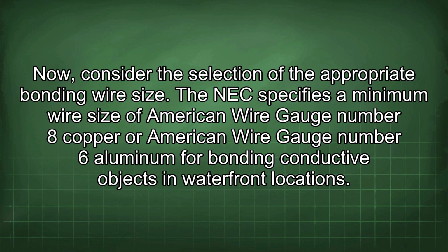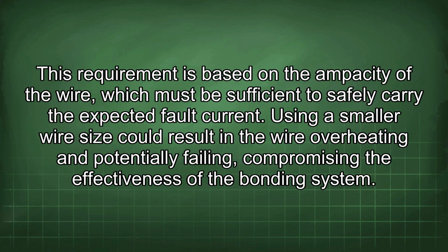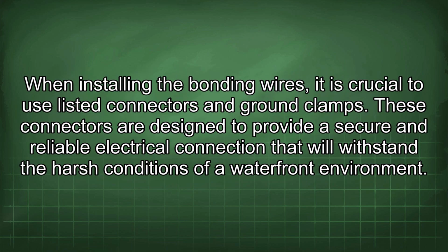The NEC specifies a minimum wire size of American wire gauge number 8 copper or American wire gauge number 6 aluminum for bonding conductive objects in waterfront locations. This requirement is based on the ampacity of the wire, which must be sufficient to safely carry the expected fault current. Using a smaller wire size could result in the wire overheating and potentially failing, compromising the effectiveness of the bonding system. When installing the bonding wires, it is crucial to use listed connectors and ground clamps.